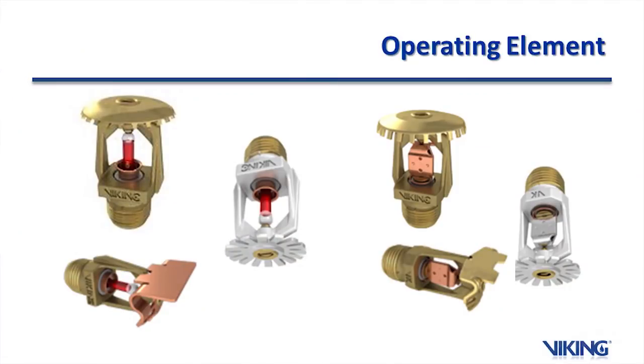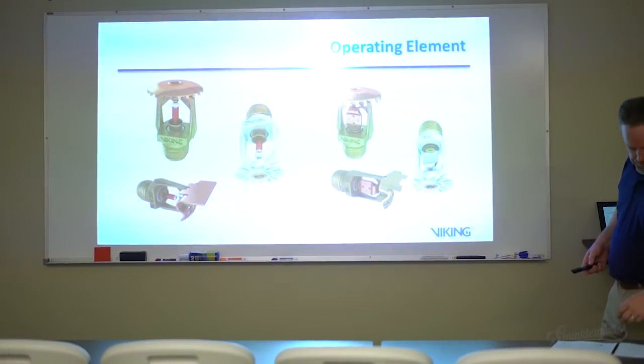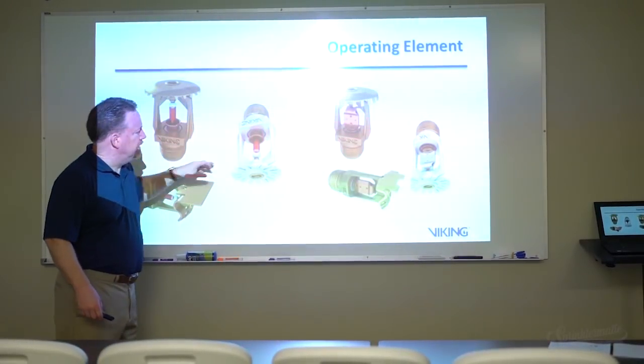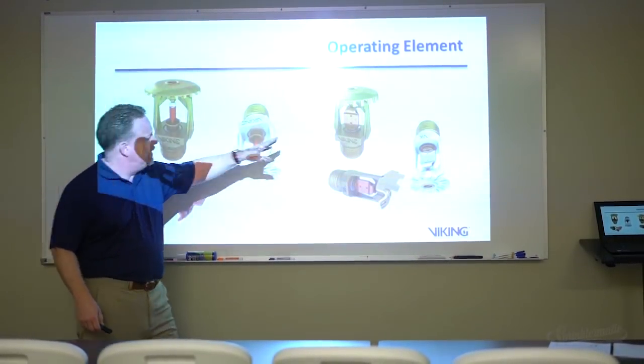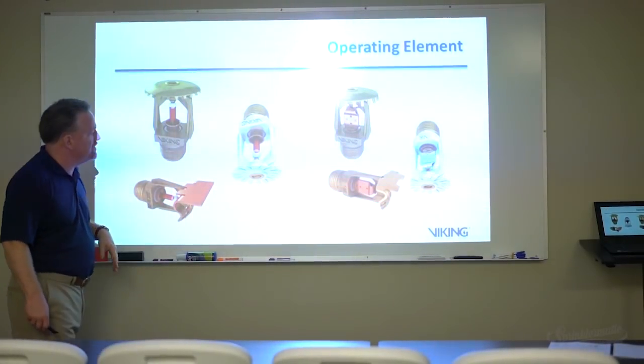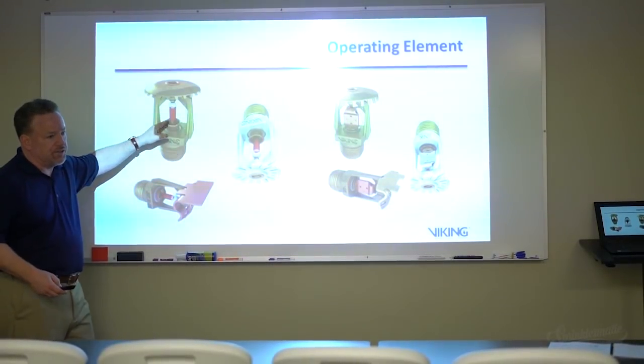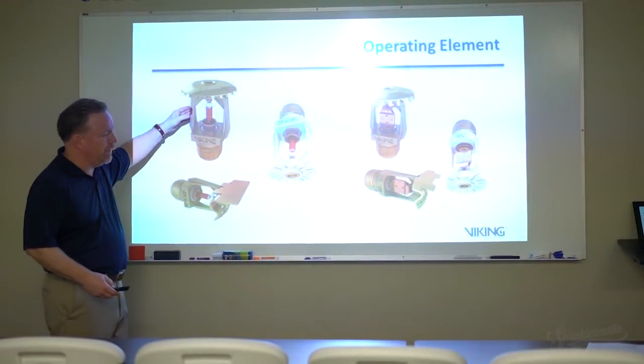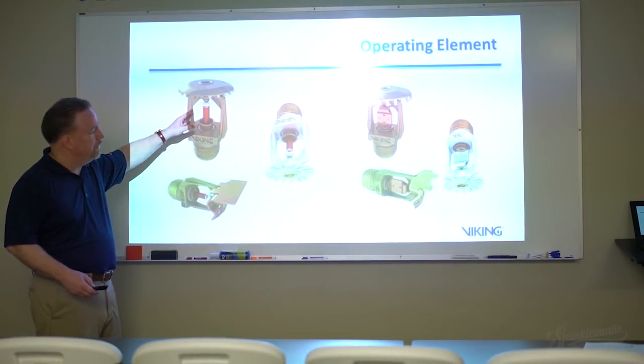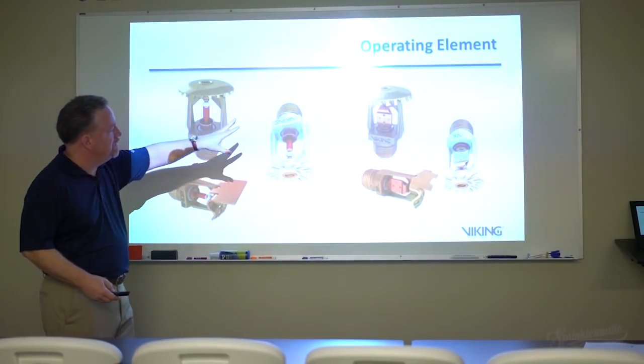To understand quick response, we look at the operating element — glass bulbs and solder link types. A red glass bulb indicates an ordinary temperature rating in the range of about 155 degrees. The same applies to solder link sprinklers. Both come in quick response and standard response versions.